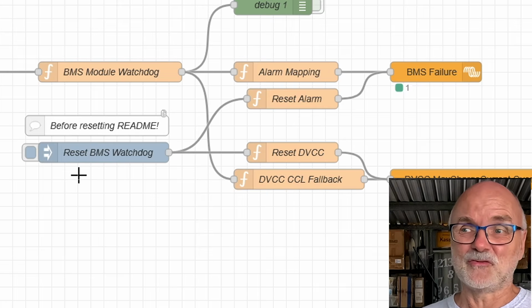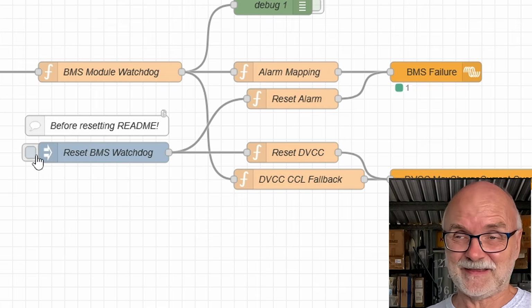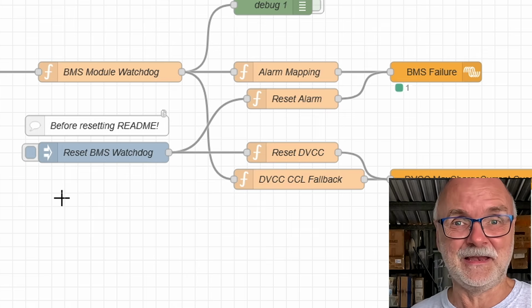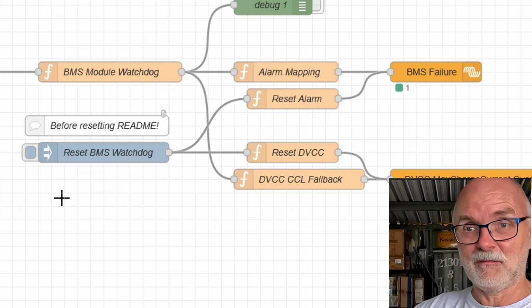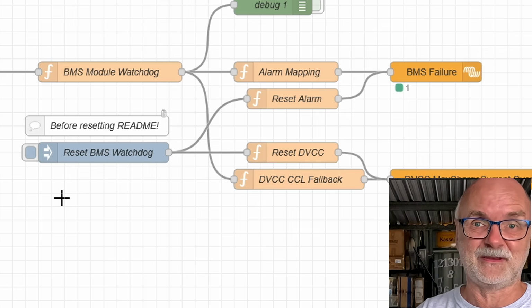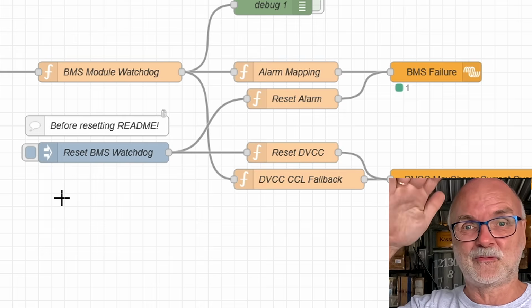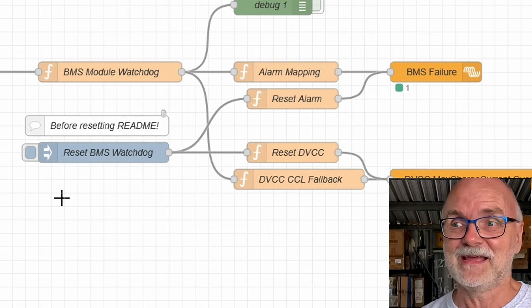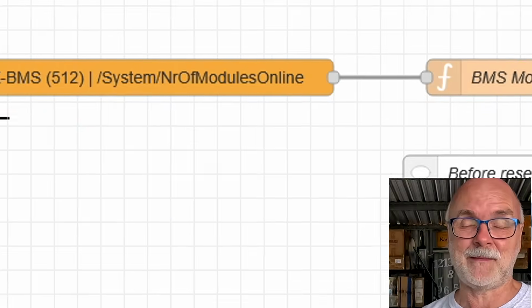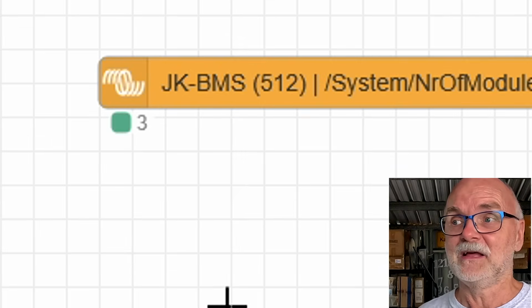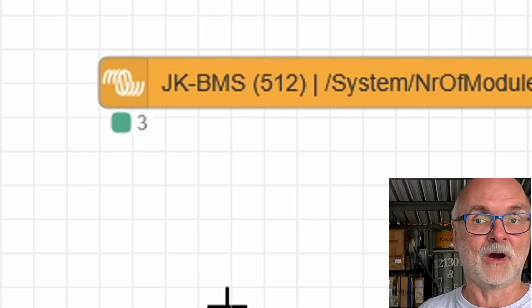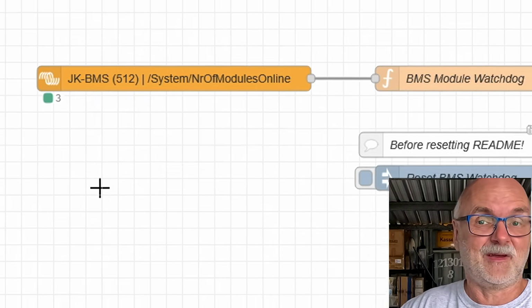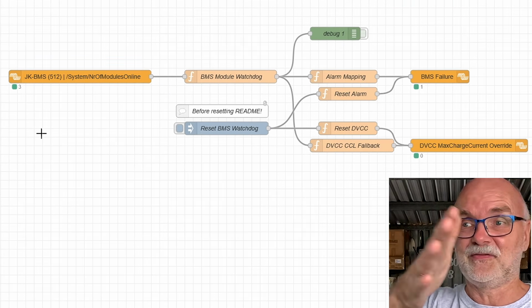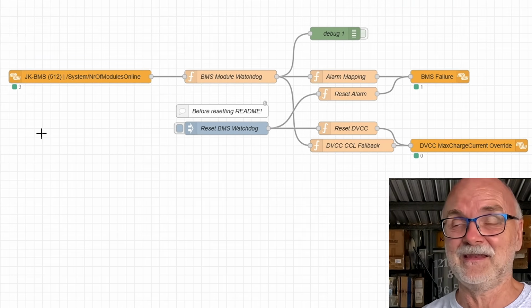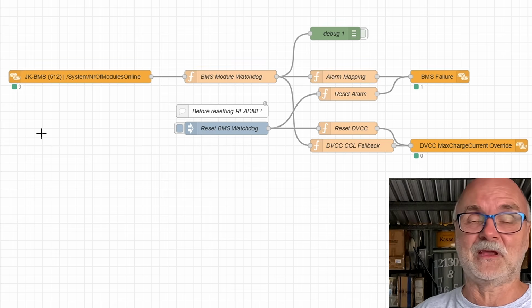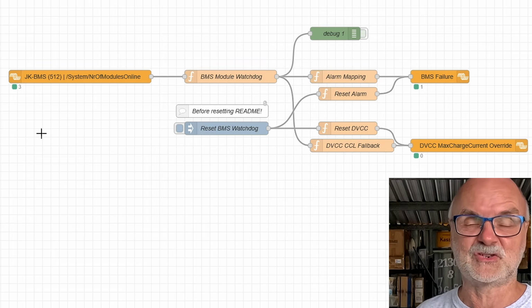I've also integrated a reset BMS watchdog, which I can press at any time if I have intentionally removed one of the BMSs. Like now, BMS 4 is out because it goes to maintenance or I don't need it anymore. I'm running the whole show with 3 BMSs. I press the button and the 3 BMSs will now be my baseline. Yeah, the alarm will clear and we're charging with 240 amps. If I lose another BMS, or another 2 BMSs or something, this whole setup will trigger again, disable charging altogether and say, whoa, something is wrong. We are setting the charge current to 0.